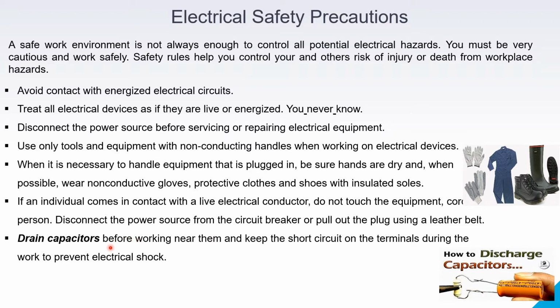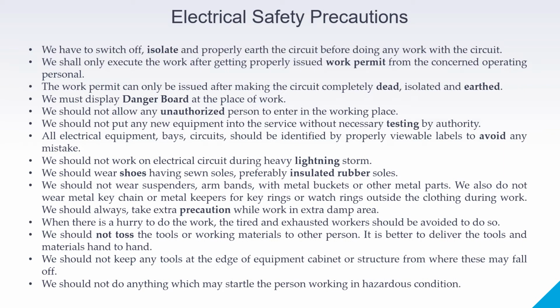Drain capacitors before working near them and keep the short circuit on the terminals during the work to prevent electric shocks. A few more precautions are: we have to switch off or isolate and properly earth the circuit before doing any work with the circuit. We shall only execute the work after getting a properly issued work permit from the concerned operating personnel. The work permit can only be issued after making the circuit completely dead, isolated and earthed.